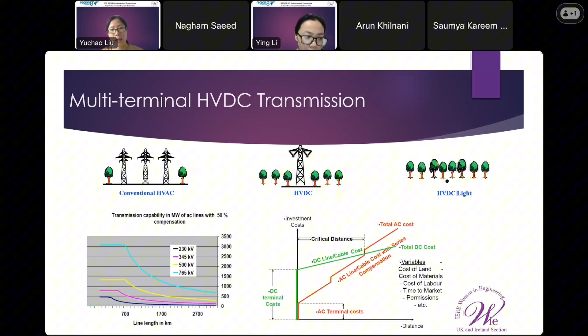Another reason is that as the transmission line length increases, for example from 700 kilometers to 3,000 kilometers, the AC transmission capacity is reduced heavily, for example by almost 50% compensation. So over a certain transmission distance, the investment cost of DC transmission is lower than AC transmission. Since most offshore wind farms are quite remote from the main grid and consumers, HVDC transmission is more suitable for offshore wind farm integration.